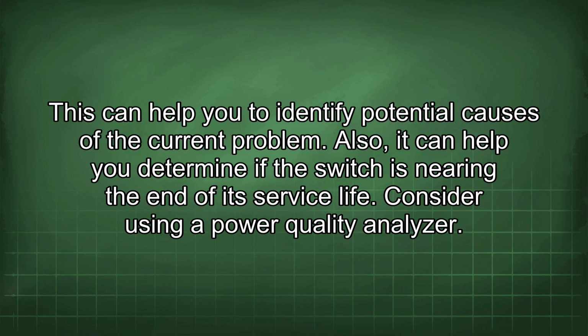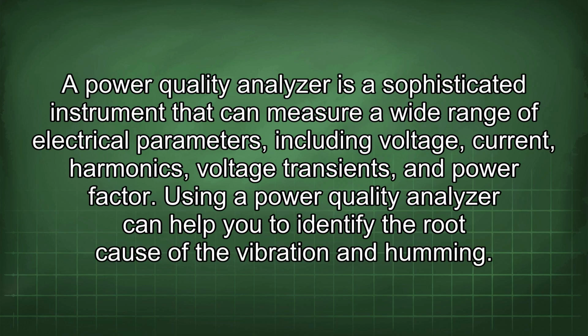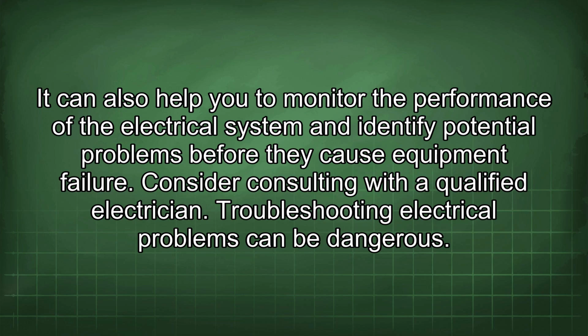Consider using a power quality analyzer. A power quality analyzer is a sophisticated instrument that can measure a wide range of electrical parameters, including voltage, current, harmonics, voltage transients, and power factor. Using a power quality analyzer can help you to identify the root cause of the vibration and humming. It can also help you to monitor the performance of the electrical system and identify potential problems before they cause equipment failure.